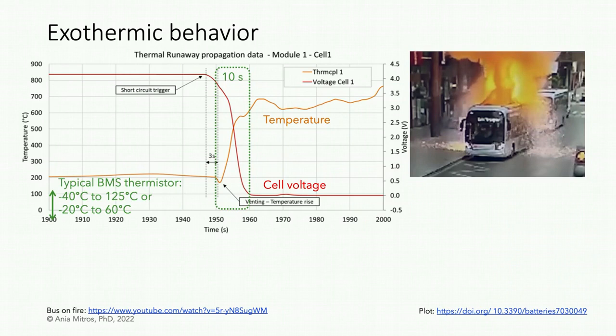This data was collected with a thermocouple on the experimental cell. In practice, most BMSs use thermistors, and the circuit is designed for a minus 40 C to 125 C temperature range, or possibly even narrower. Also, with only a few thermistors within a large battery pack, if the cell that enters thermal runaway is not immediately near a thermistor, significant time may pass before the thermistor registers a significant temperature rise. It turns out that voltage is a better way to detect that something has gone very, very wrong. And also, a BMS can't actually do much in this situation.